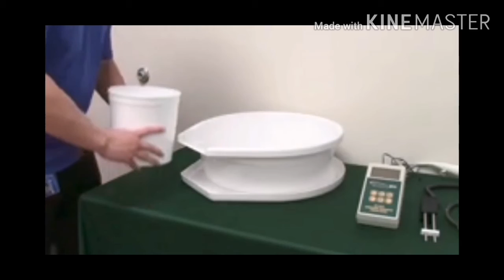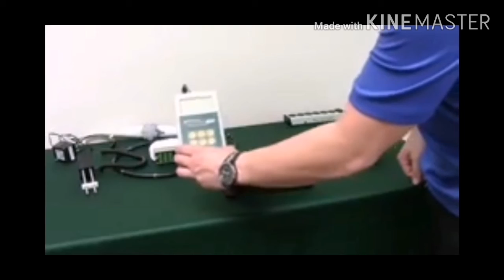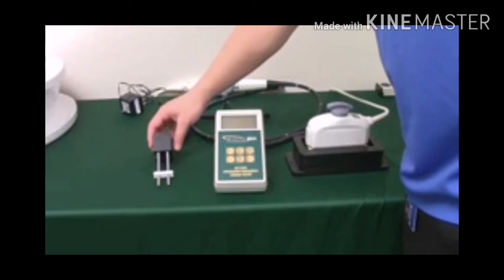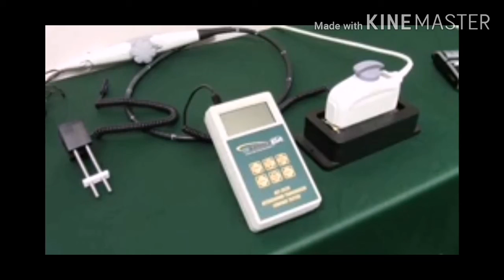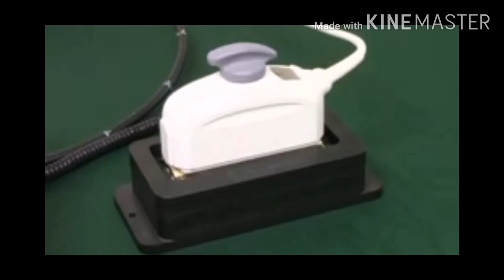Step 2. Connect equipment. Start by plugging your transducer adapter into one of the 2 ports on the top of the ULT 2020. You can use either port. Next, plug the ultrasound transducer into the adapter. The adapter should click into place. Look in your ultrasound transducer manual for OEM recommendations on connecting your transducer. Once that is attached, plug your dual-prong conductivity probe into the second port on the top of the ULT 2020. You can use either port. Now all parts should be fully connected. This includes the ULT 2020, dual-prong conductivity probe, transducer adapter, and ultrasound transducer.